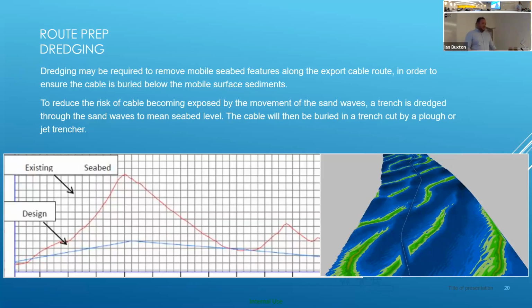So that's something we don't want. To mitigate this, we have to dredge out a channel in the seabed, much as a civil engineer might design a road through rolling countryside. You dredge a channel through the sand waves to give you a design seabed at the stable seabed level, so that when you bury the cable below that level, it won't get exposed over the lifetime of the project. On East Anglia 1, we used a very big vessel called the Francis Beaufort for this, which I'll show you later.